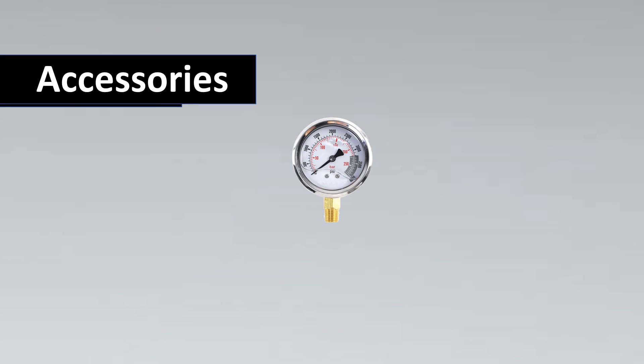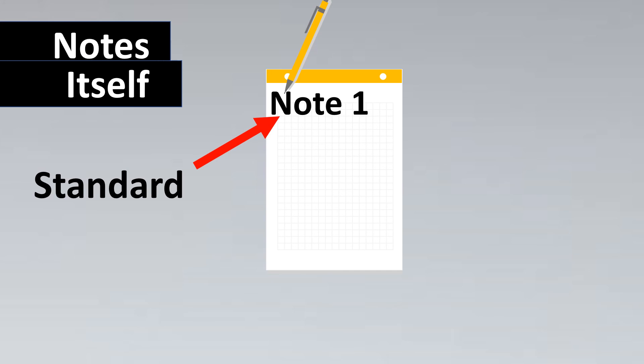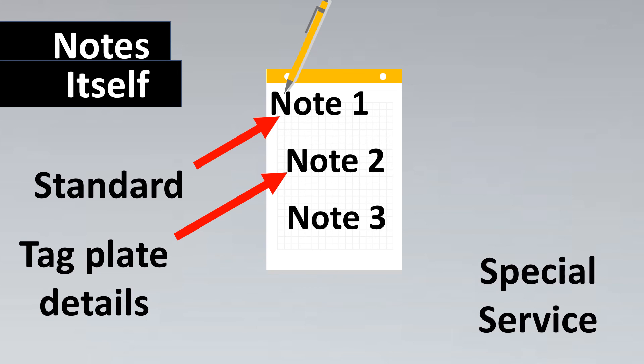The second sub-part is accessories. For a pressure gauge you might require a siphon or a snubber — used when there's pulsating discharge in the line, such as at a pump discharge. For a control valve you might require a gauge. Accessories depend on the instrument type. The third sub-part is the notes section, used for details that don't fit in the form — for example, NACE certification requirements, applicable client standards, tag plate details, or special service notes like hydrogen service requiring gold plating.